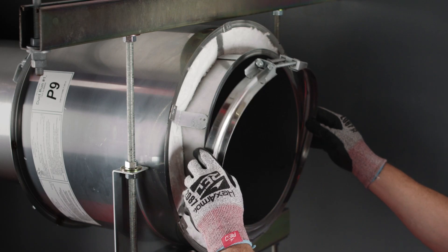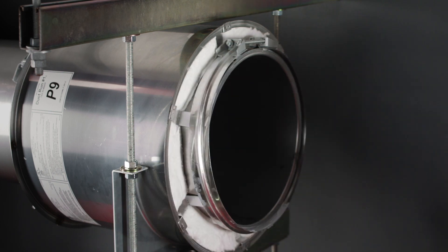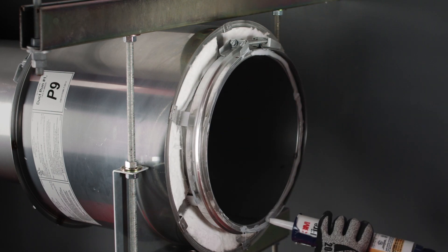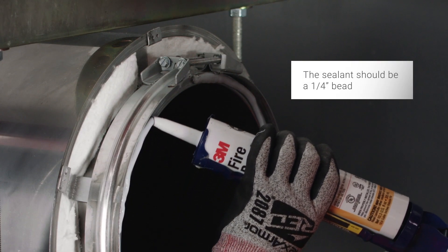Place the V-band just past the duct flange, leaving enough room for the next duct section. Apply a continuous quarter-inch bead of sealant around the flange to be joined. The sealant should be about the width of a pencil.